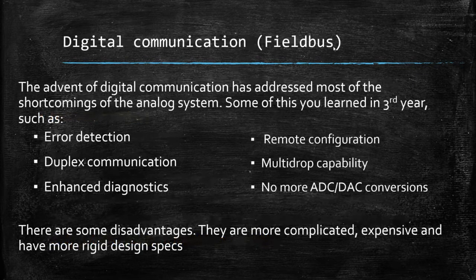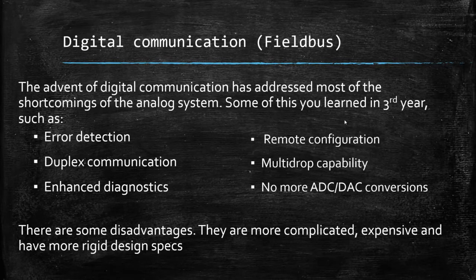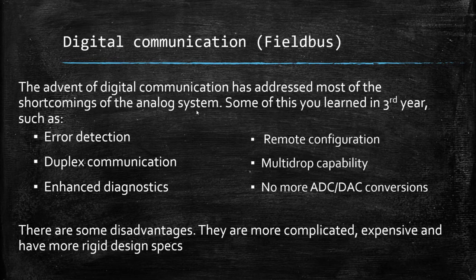Digital communication, often called field bus — not the trademark Fieldbus, but field bus meaning a bus with everything branching off of it, like we talked about in third year with HART. It can have up to 15 devices on the bus, all with individual addresses between 1 and 15. You can think of a bus like a power line — a couple of wires running overhead and everybody that needs power takes two wires off of it. Some protocols carry just data, and some carry data and also power.